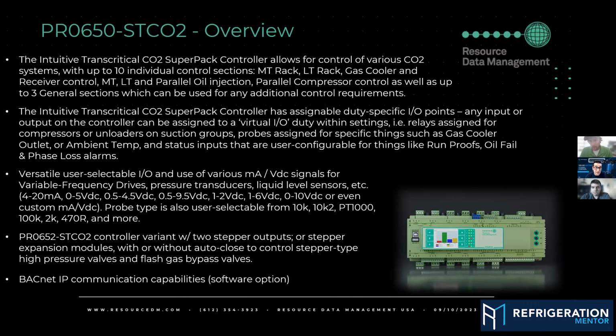And Chris, I know you've been doing tons and tons of technical support for the RDM product over the years and even on CO2. What are some of the things that technicians like a lot of the calls that you get for the support for CO2 systems? So CO2 systems, I haven't done a whole lot. That's more Cody's thing right now. But I've done hundreds of standard HFC racks, and it's probably very similar in where you'll see maybe sensors being misplaced or miswired. We've had a lot of issues with run proof inputs being swapped around for compressors, and then compressors will get locked out, and technicians are just kind of like, well, something's wrong with the program. And what it really is, it's actually OEM wiring that's wrong.